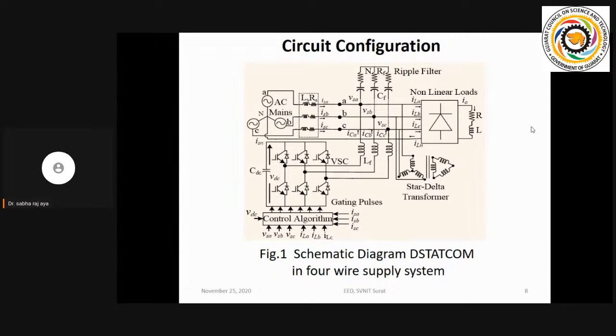Okay. After this, here we have used one delta star connected transformer to compensate the neutral current. So here the central point of the star connection we can connect to the neutral wire. You know, there is the neutral current from the load side, whatever neutral current you are going to observe, and the supply side, whatever neutral current you are going to observe.